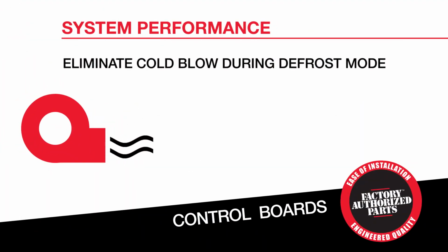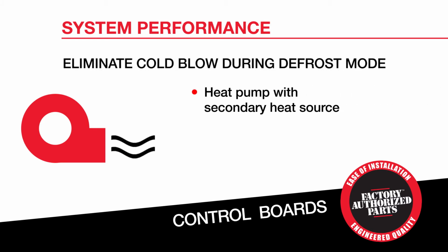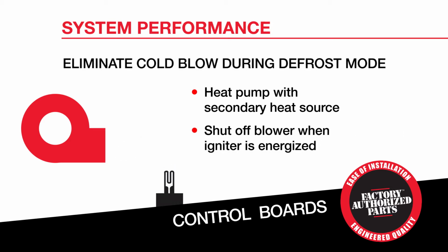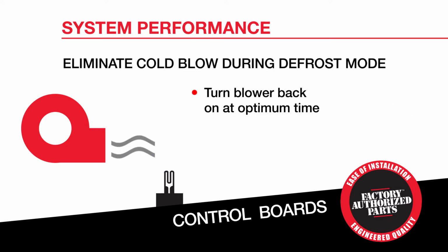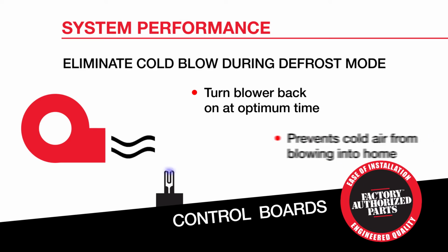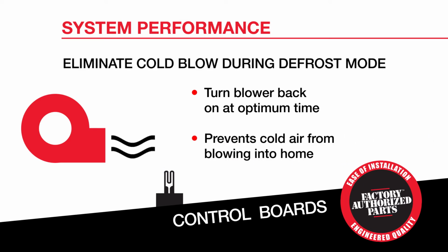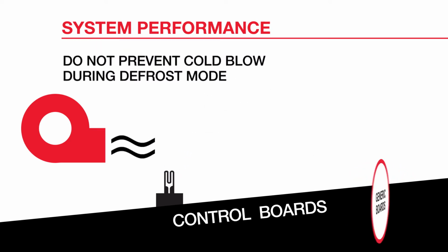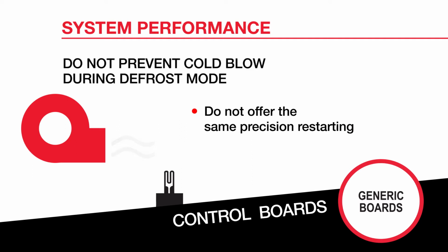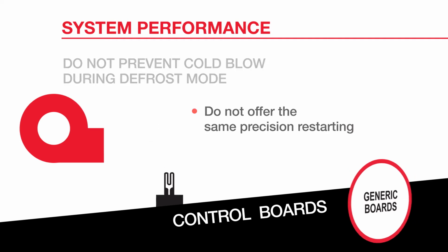One way they do this is by eliminating cold blow during defrost mode. In situations involving a heat pump with a secondary heat source, factory authorized parts boards are designed to shut off the blower when the igniter is energized during defrost mode. And then they turn the blower back on at the factory engineered optimum time. This prevents cold air from blowing into the home, and that means happier, more comfortable customers. Some generic boards do not offer the same precision when restarting the blower.